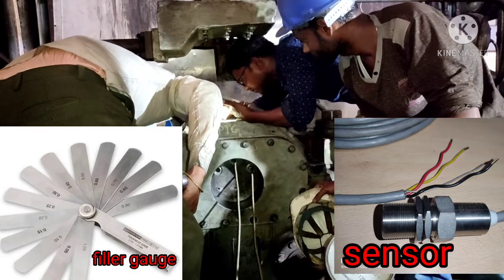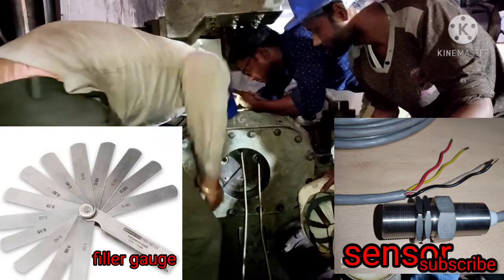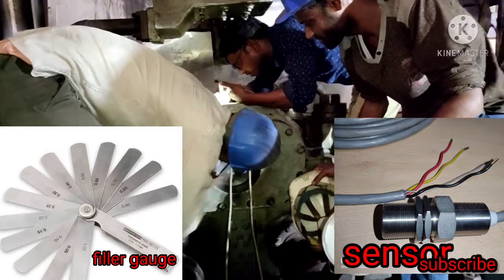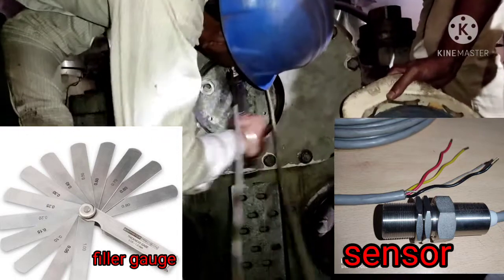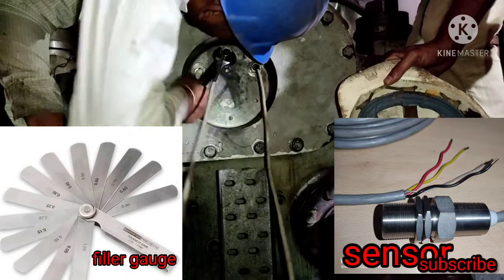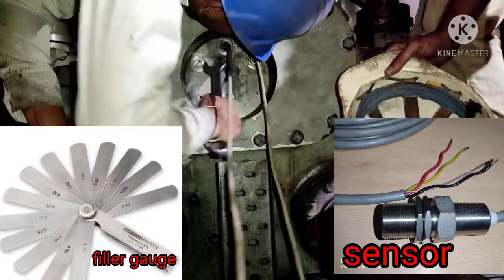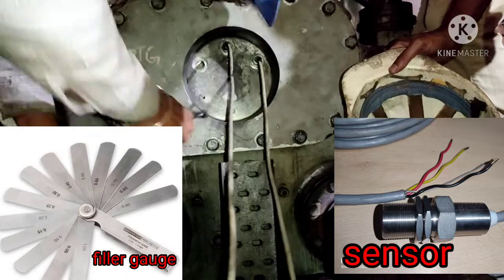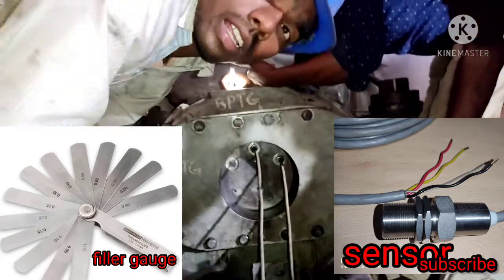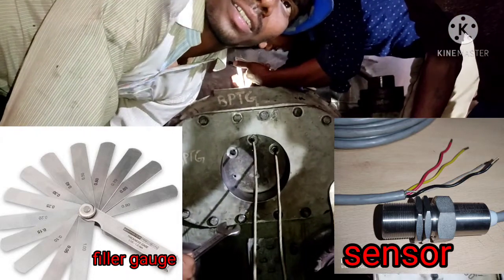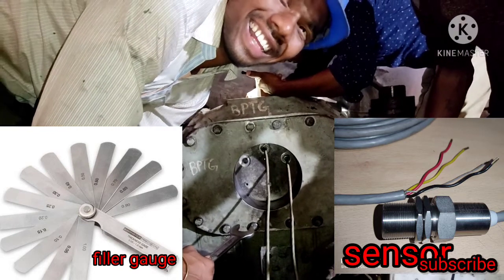Mounting process is going on. This is the feeler gauge. Through this feeler gauge we maintain the gap between the sensor tip and turbine teeth. It is very essential because we have to maintain a 1.5 mm gap.